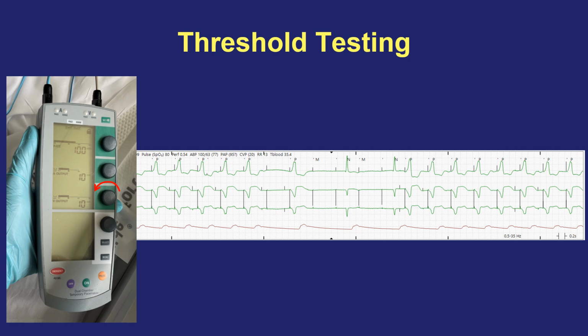In standard pacemaker leads, in permanent pacemakers, the metal that is interacting with the myocardium, that's touching it, is a very different type of metal, and there is steroid that is impregnated in that distal electrode to reduce inflammation. And that's how we achieve a very low chronic stable pacing threshold in permanent pacemaker leads, but that is not present in these temporary wires, and so they have a limited lifespan in terms of their effectiveness in capturing myocardium.